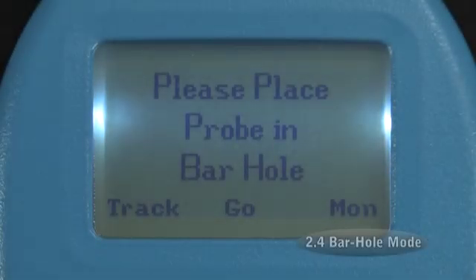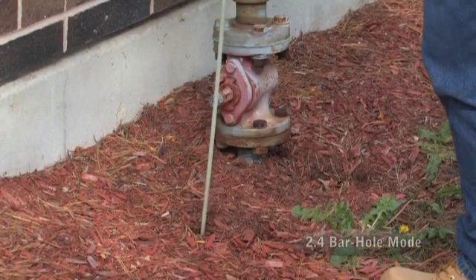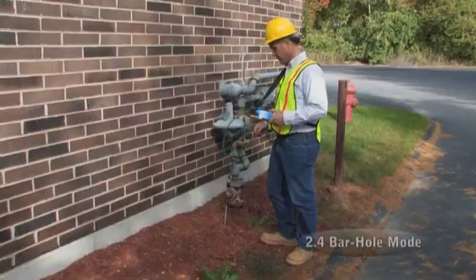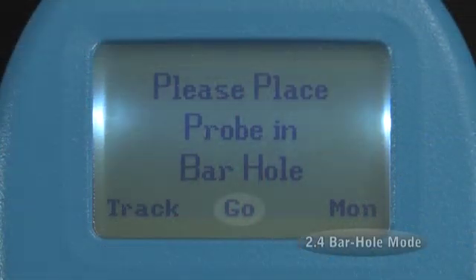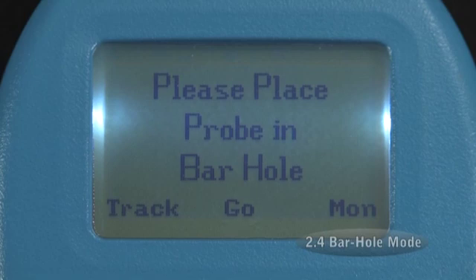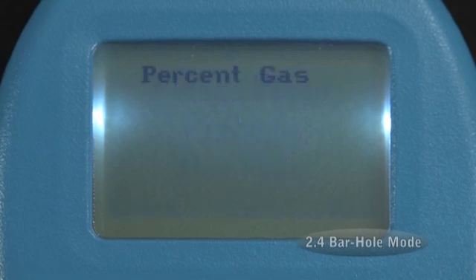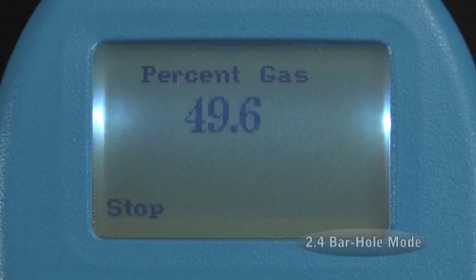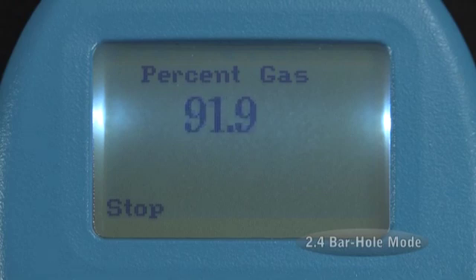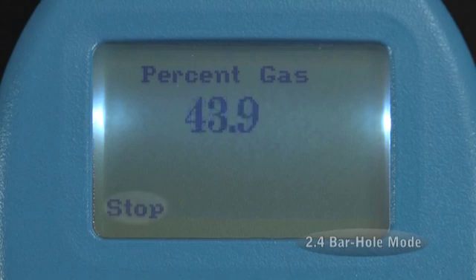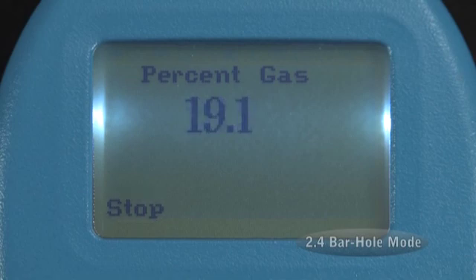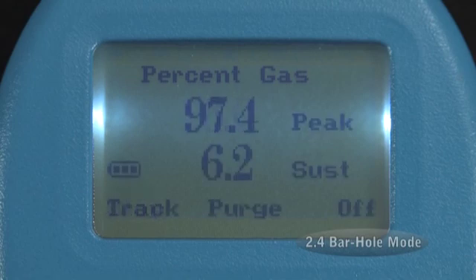Once the instrument has been purged, you will be asked to place the probe in the bar hole. Once the probe has been inserted, press the middle button marked Go. You will hear the detector's pump motor begin to run again, and the Explorer will pump the hole for 15 seconds. While the hole is being pumped, the display will show the percentage of gas detected. If during this time you need to stop for some reason, for example if water is being drawn into the probe, press the left button to stop the pump. If you do not stop the pump, it will automatically stop at the end of 15 seconds.